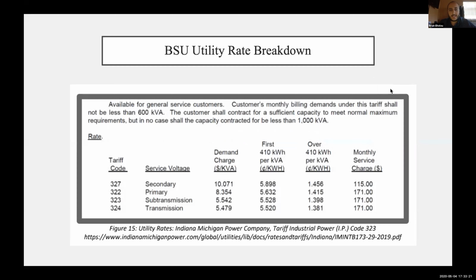The university is billed by the Indiana and Michigan utility company based on the gross meter readings and peak demand events at this substation. As bulk purchasers of electricity, they are charged a base rate derived from the 15-minute block of time during the month with the most extensive electrical usage. The peak usage, expressed in kilovolt-amps, is multiplied by $14.72 to determine their base rate for the month. Then their total month's usage in kilowatt hours is multiplied by 1.088 cents per kilowatt hour and added to their base rate to determine their final bill for the month. Their greatest financial savings comes from reducing peak usage. Next slide, please.